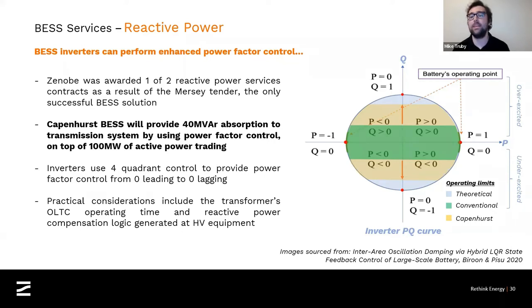What the graphic on the right is trying to demonstrate is that historically, inverters were somewhat limited in how much reactive power management they could provide. Modern inverters have become much more efficient and much better at handling the extremes of operation. The system we have installed at Capenhurst is similar to other systems on the market. I will stress that whilst Capenhurst is unique in delivering this service first, this is not necessarily unique to the Capenhurst battery storage system. We're able to push those limits closer and closer to the theoretical operating capability. That means the Capenhurst system can provide those 40 MVArs of reactive power absorption whilst still providing active power, and we can do that at 100%, 100 megawatts of active power trading.